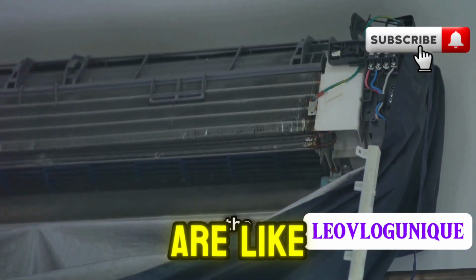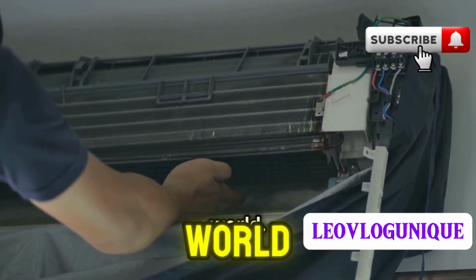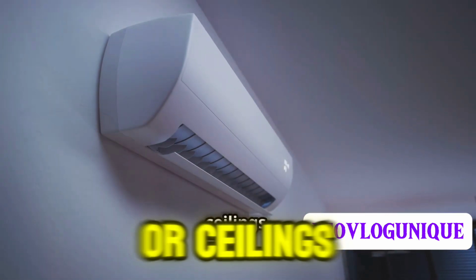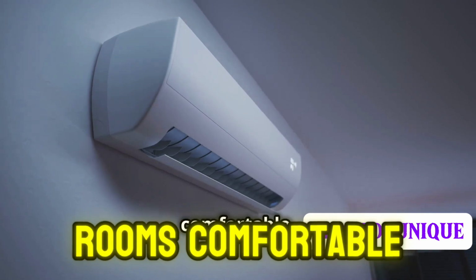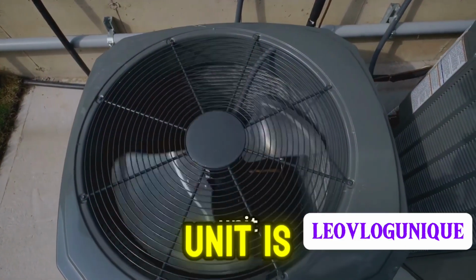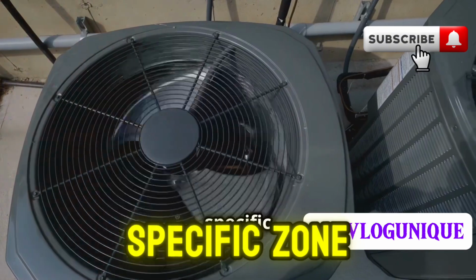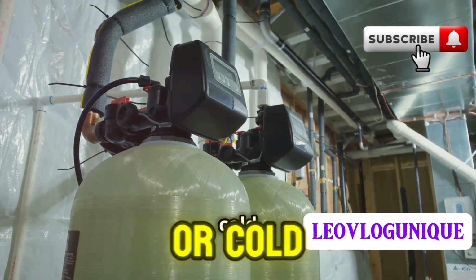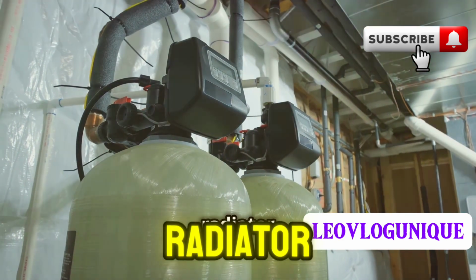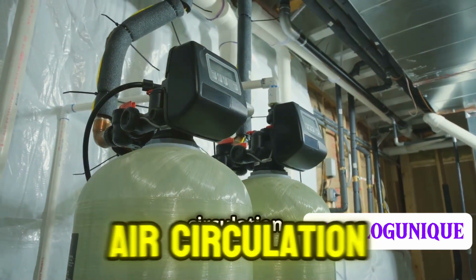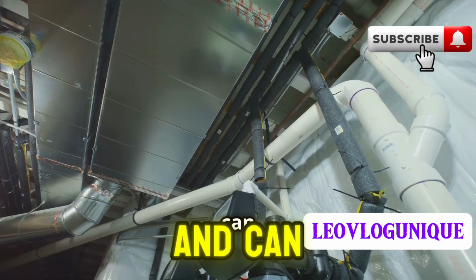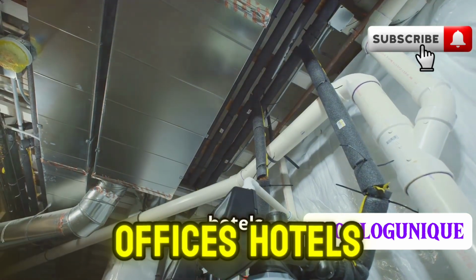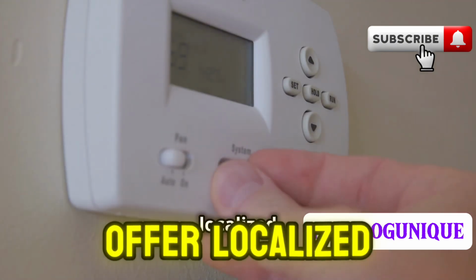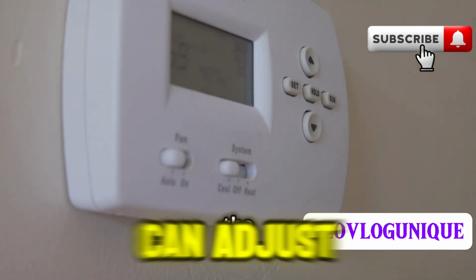Fan coil units are like the unsung heroes of the HVAC world. They're those boxy things you see on walls or ceilings, quietly keeping rooms comfortable. In simple terms, a fan coil unit is like a mini air conditioner for a specific zone or room. It doesn't make its own hot or cold air though. Instead, it relies on hot or cold water from a central source, kind of like a radiator but with a fan for better air circulation. These units are super versatile and can be found in homes, offices, hotels, you name it. They offer localized temperature control, so you can adjust the temperature in each room without affecting the whole building.